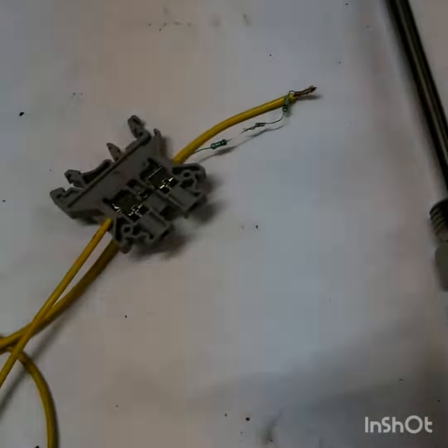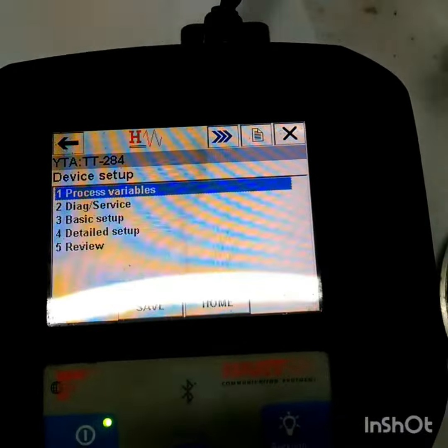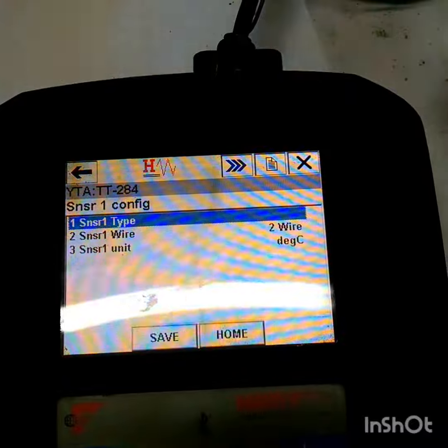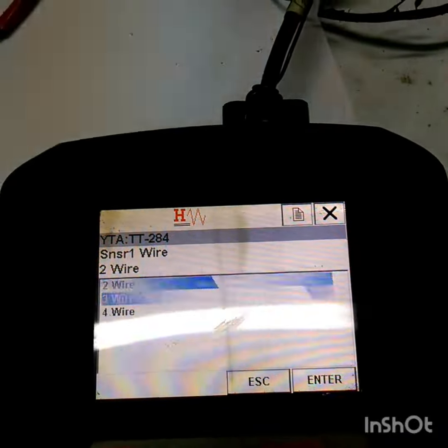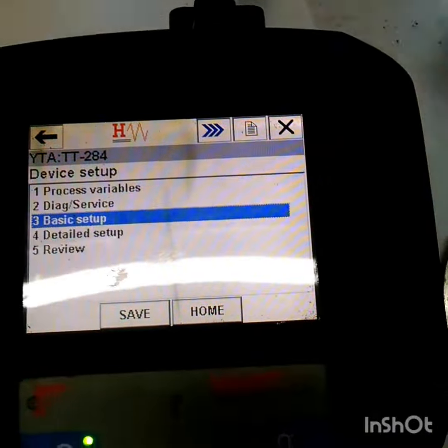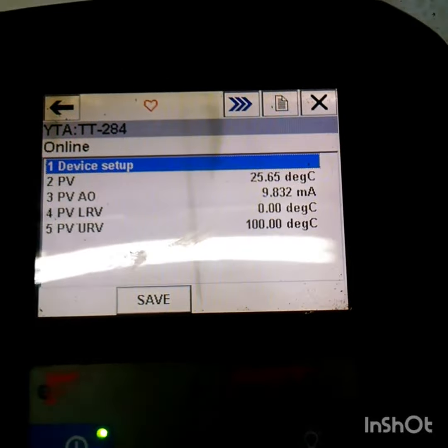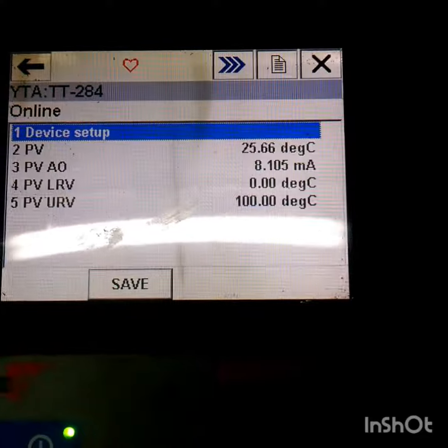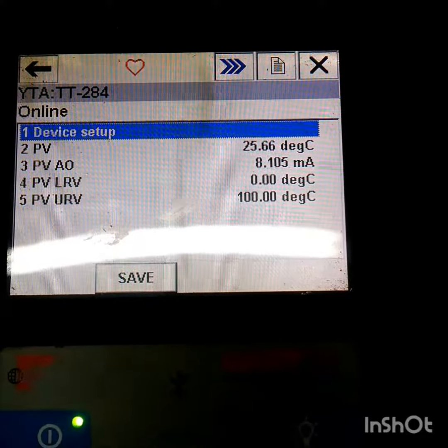I am changing the configuration to three-wire in the HART communicator. You can see the reading has come back down to normal room temperature — 24 to 25.66 degrees centigrade.